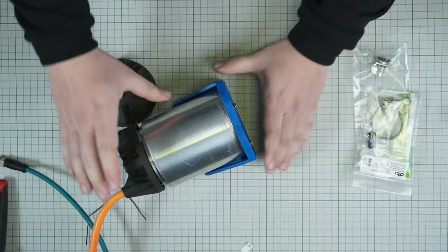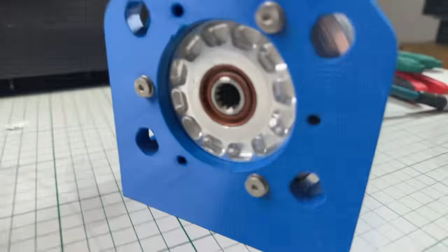What you also need to take care of is the motor mechanical parts of the system. So when you are starting a dyno test of the motor, I will show you around with my phone. There is the shaft seal here. It's a crucial part of the motor, and it's prone to damage if you are not using the system properly. So whenever you are doing a bench test or a dyno test, make sure that you are properly lubricating this during the sessions, because otherwise it could be damaged, and in the worst case situation you can even damage the shaft itself. So it's a critical part to properly lube up if you are using it as a test bench or so.